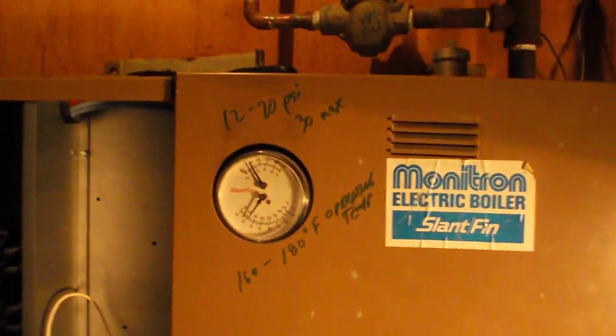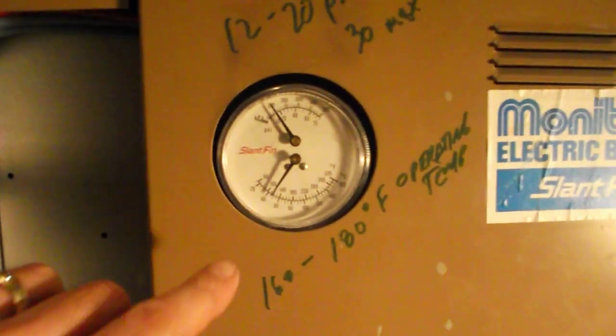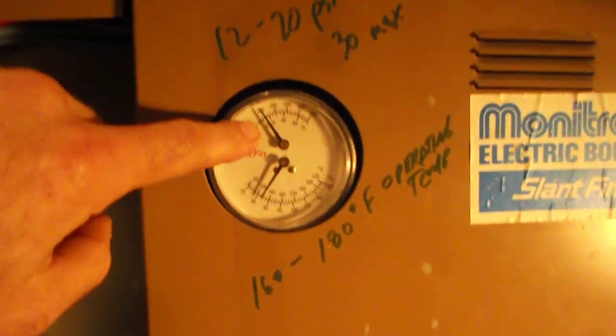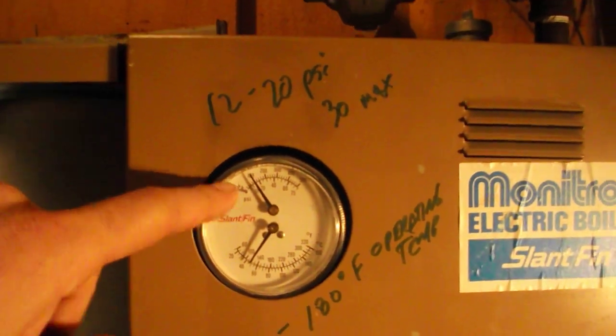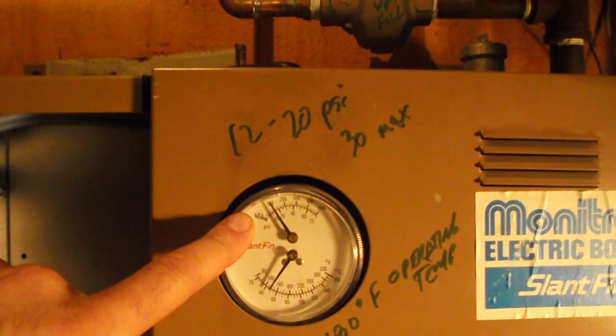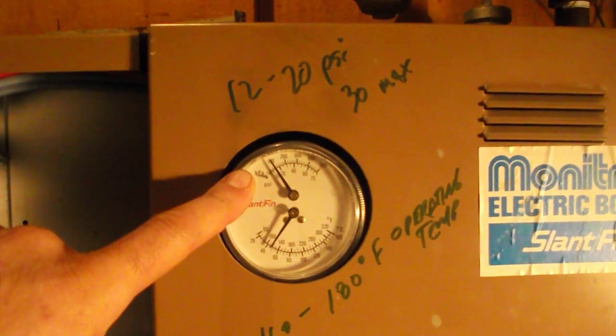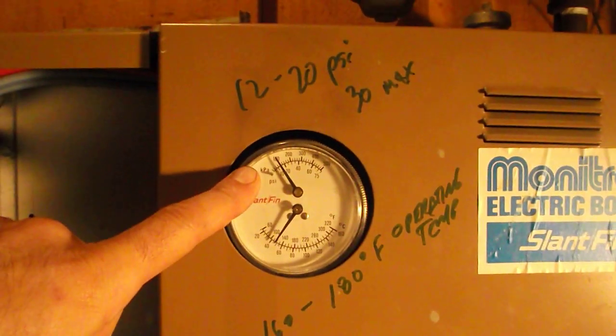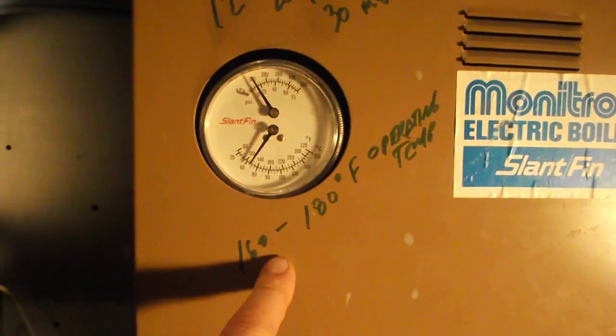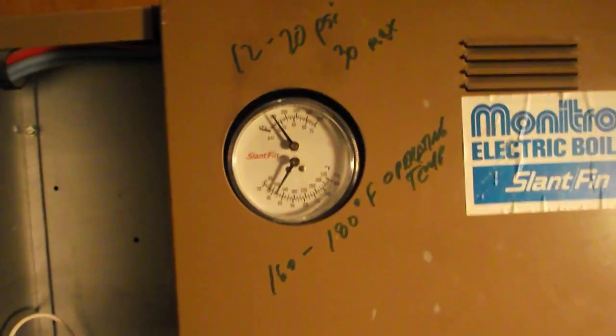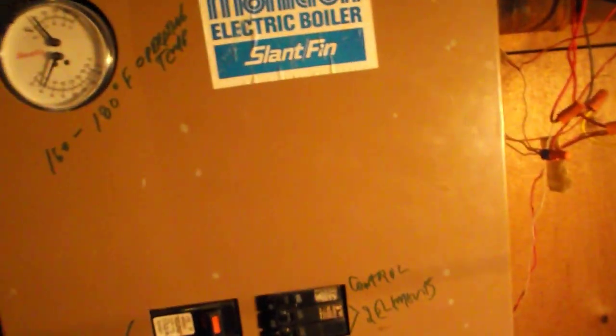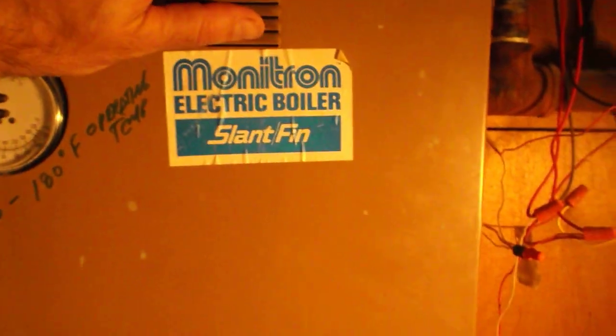So on the front here we also have a pressure gauge, and someone who likely installed it identified 12 to 20 psi as the target range with a 30 psi max, and then the target temperature of 160 to 180. And I'll take this cover off. This is a Monitron electric boiler. It's old, it's probably 40 years old, and on the inside is the wiring harness.